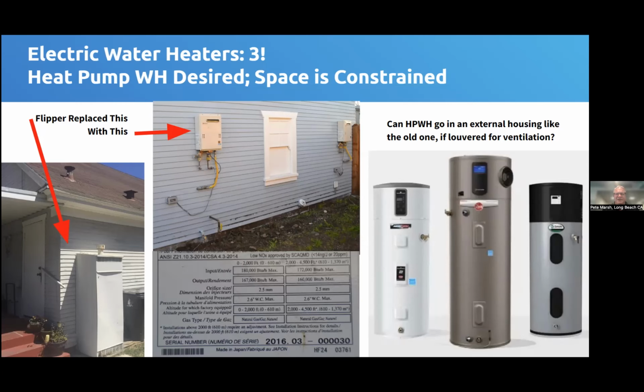And that was simply 8-gauge wire on a 30 amp circuit breaker. That's the size for almost all of the heat pump water heaters out there. And there are, as Sean loves to point out on his shows, increasing options for water heating on a watt diet. If you don't have a 240 volt circuit available, you can plug into a 120 volt circuit. You just won't have as fast a recovery rate, but once you've heated up the water in the tank, you'll be just fine.